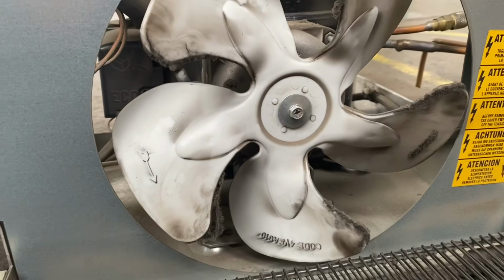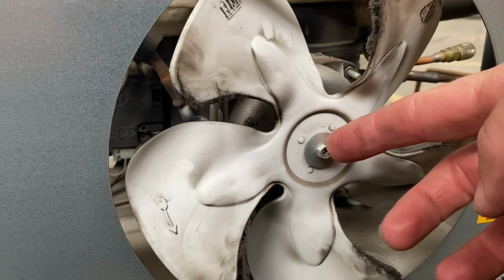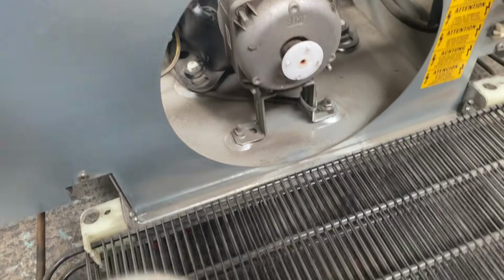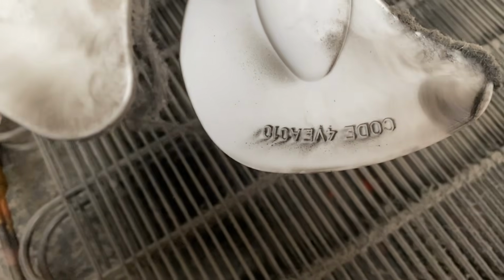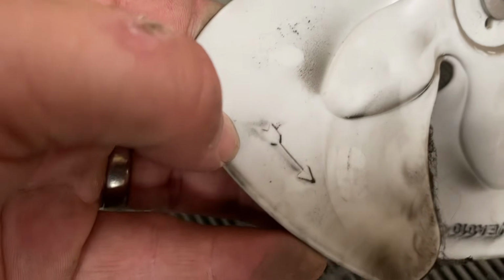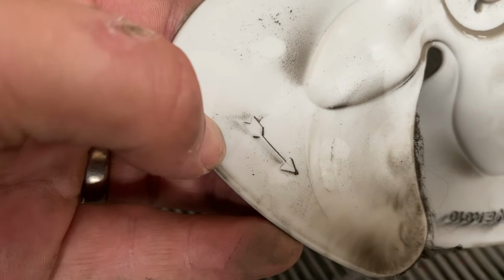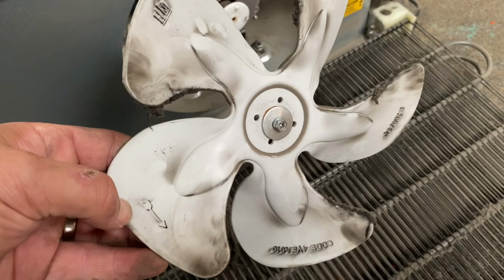Okay, now with the chiller completely removed, you can see you need to take this screw off to take the actual fan blade off. So once you've removed that screw, remove the fan blade, and just take a note of the actual arrow pointing down on one of the fins. So you need to make sure when you put it back on later that you put it back on the same way that you take it off.